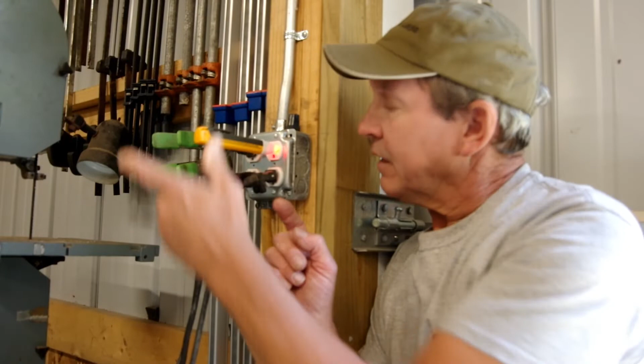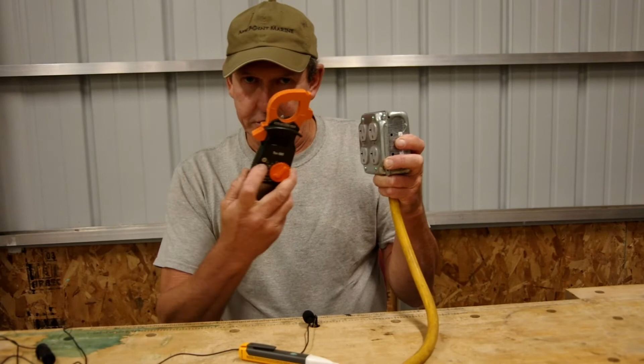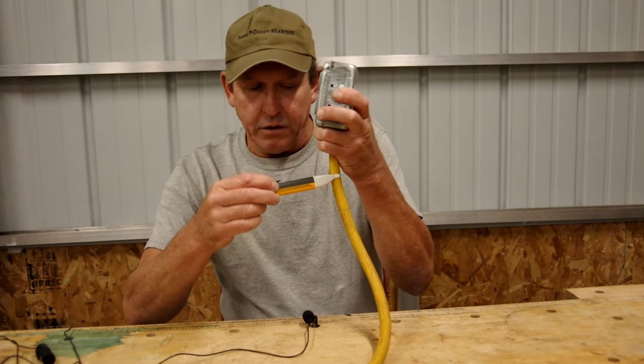But I wanted to share this with you because it's kind of interesting. I'm going to test this outlet to see if it's energized. I put my probe in, and I don't have an alarm. Let's assume this is de-energized. Let's use this non-contact voltage detector, the one built into my multimeter, and see. Okay, seems like it's off. Let's check the cord going to it. It's energized. What gives?